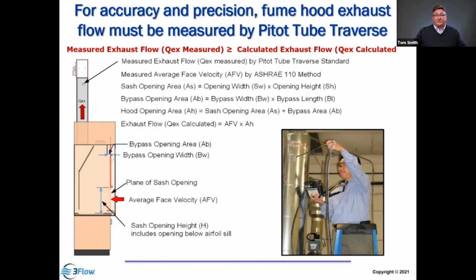Now, if the reverse is true, we measure 1,000 and it's 1,100 in the duct, that's the right value, the right direction. At least we know that then the theory is correct, and it should be closer to reality. So again, just remember, the flow in the duct should be greater than your calculated flow through the face. The calculated flow through the face is only as good as the measurement technique that was used to produce the average velocity.